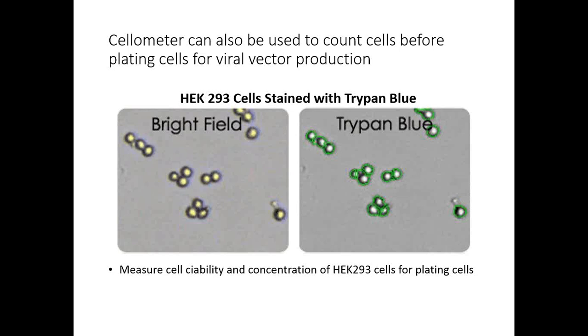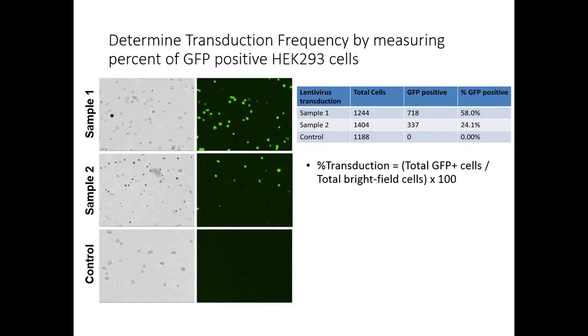The cellometer can also be used to count cells before plating for viral vector production. In this example, HEK-293 cells stained with trypan blue are counted using the cellometer Auto T4 to ensure the correct number of cells are plated. Additionally, the fluorescence capability can be used to look at GFP-positive cells to measure transduction frequency — counting total cells in bright field and GFP-positive cells in fluorescence to calculate percent transduction efficiency.